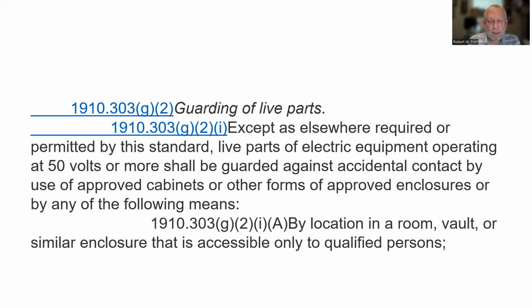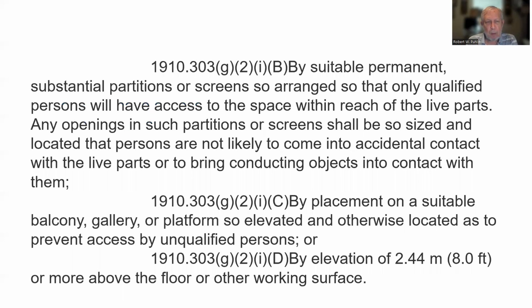Guarding of live parts. Except where elsewhere required or permitted by the standard, live parts of electrical equipment operating at 50 volts or more shall be guarded against accidental contact by use of approved cabinets or other forms of approved enclosures, or by any of the following means: by location in a room, vault, or similar enclosure that is accessible only to qualified persons; by suitable permanent substantial partitions or screens so arranged that only qualified persons will have access to the space within reach of the live parts.